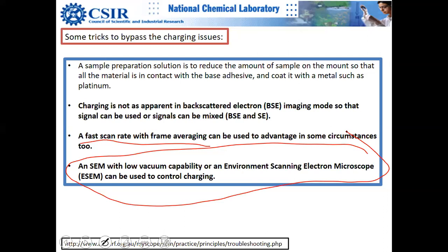There is a very interesting mechanism in environmental SEM. Low vacuum obviously compromises the resolution. Otherwise you could always throw away conventional SEM and welcome ESEM, but everything comes at a cost. In ESEM you compromise with the resolution, but then you have no problem with charging, and you don't need any coating if you are working in low vacuum. I'll tell you the trick later on.